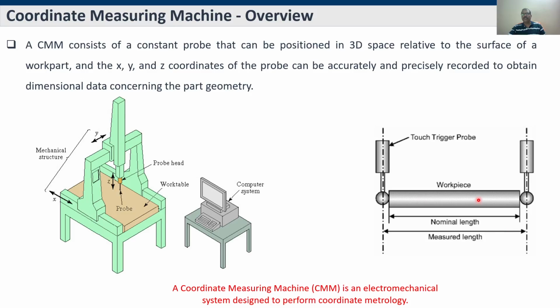For example, this is the workpiece which is going to be measured using our CMM machine. The probing head will be here, and this probe will have a circular type, sphere type or ball type tip. So this is what you want to measure. Initially, the probe head will move down the z-axis and touch the workpiece. Then it understands the initial location. Then again it will go up and move forward. Either the probe may travel or the workpiece may be moved. Mostly the probe travels. For example, if it is a lengthy component, then the table will be moved. But here it will go up and be placed over here.